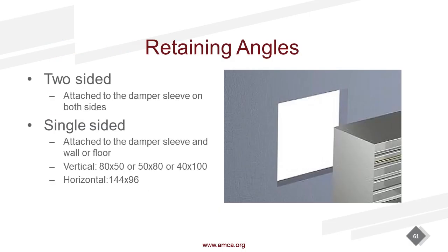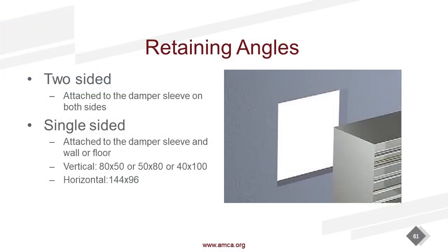Here's your typical single-sided angle. So shaft walls, 1.5 hour rated dampers up to a certain size listed up there can be used with the single-sided angle. We put the fastener in the barrier, put the fastener in the sleeve. That keeps that damper in the wall. And it's good for, again, dampers that don't have that access on the opposite side. But then you have your 2-sided angle. The fastener for a 2-sided angle only goes in the damper sleeve.